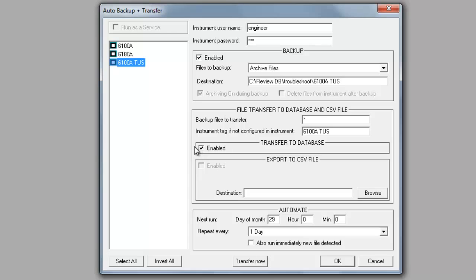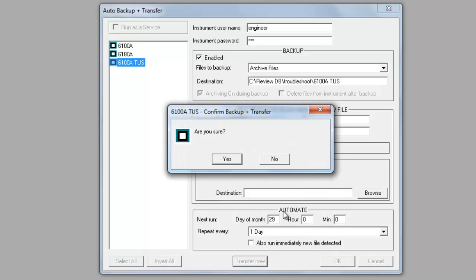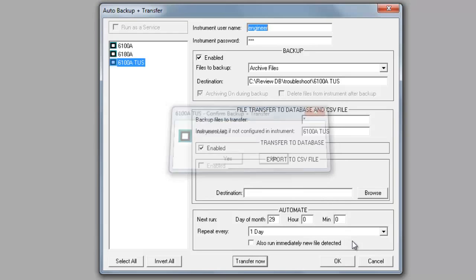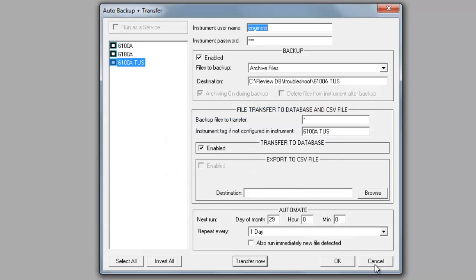What is optional, however, is this enable tab underneath the transfer to database. I'd recommend utilizing this because without having the data in the database, you can't recreate the chart. So if you click on enable for both backup and for transfer, then hit transfer now and confirm, it's going to go out to the recorder or the Nanodac, log on to that unit, and pull everything over into the master archive folder, then transfer it into your database. When you transfer it into your database, that data now is at your fingertips for recreating charts based on the data you've collected.